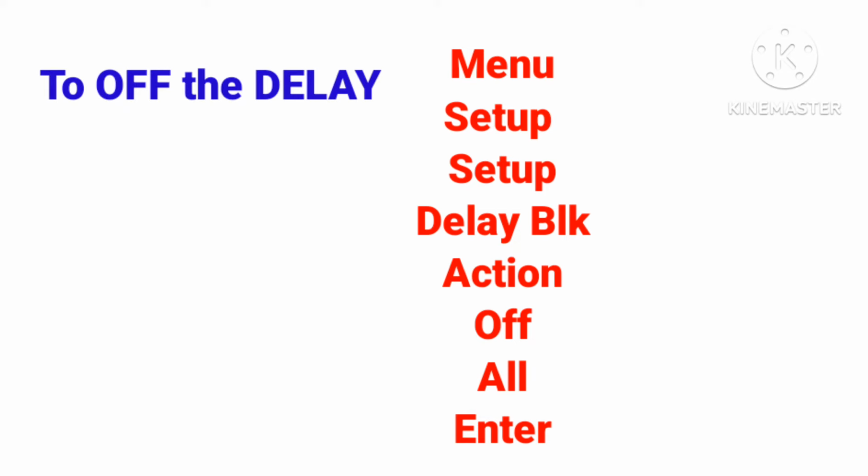And if you want to turn off the delay block temporarily, you go into any panel and say there is a delay there and you don't need any delay there, you can also turn off the delay: menu, setup, delay block, action, then off, then all, then enter. Okay, you can turn off any delay, or particular delays, or all delays.